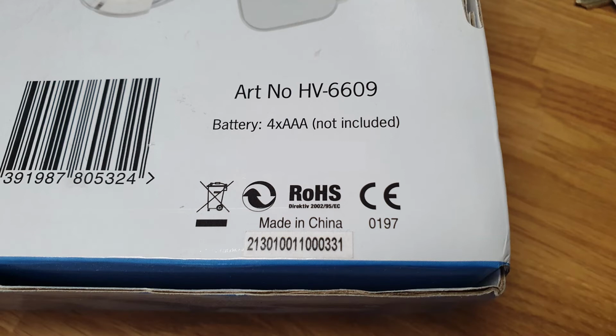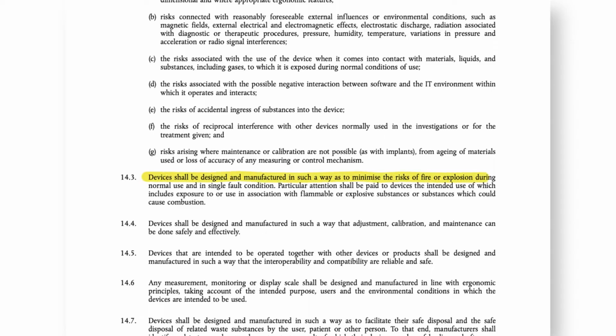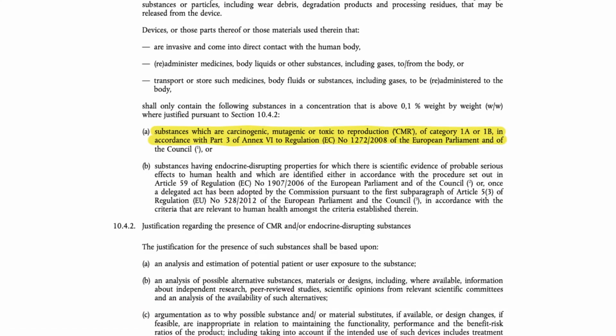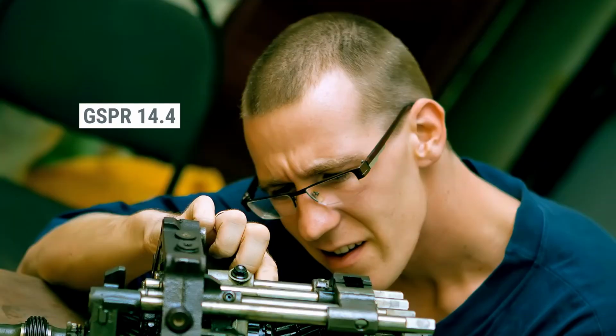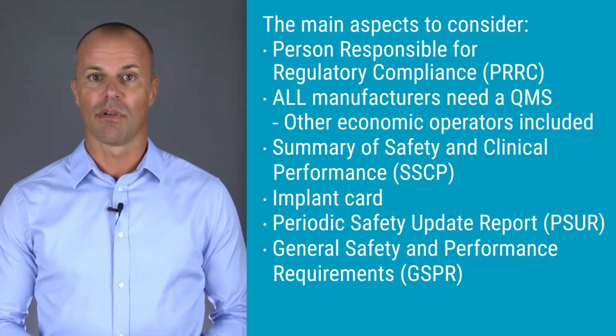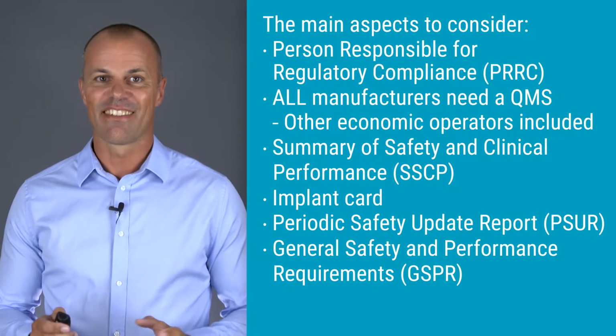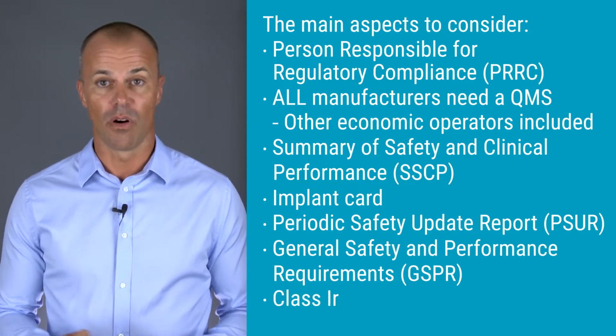Just to mention a few interesting requirements under GSPR. You need to write the words medical device on the label, and please note that there is no harmonized symbol for this right now, even if available in a standard. There are new requirements regarding flammable or explosive substances. Actual limits for some harmful substances like carcinogenic or mutagenic substances. Devices shall be designed and manufactured in such a way that adjustment, calibration, and maintenance can be done safely and effectively. Last but not least in this non-exhaustive list is the new risk class, the Class 1 reusable or 1R.